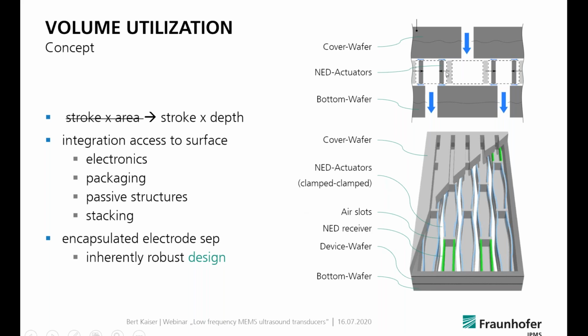With this approach, as described in the slide, we have also an inherently robust design, and what is meant here is that the electrode gap, which is within the electrostatic drive, as I showed on the previous slide, is shielded by the cover and bottom wafer, so it's within this bar here, and every particle is prevented from getting into this gap because of the concept. What else is to be said about the design is on the next slide.